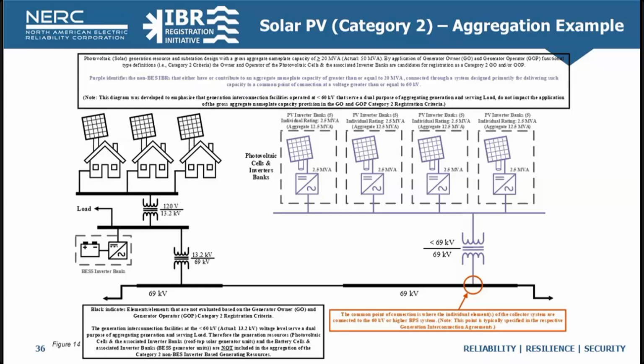Common point of connection here, as we identified by the orange circle, is at a voltage of 69 kV, which exceeds the 60 kV threshold. Therefore, identified in purple are the facilities that meet the Category 2 criteria, and as a result, the owner and operator are candidates for registration as a Category 2 generator owner and a Category 2 generator operator.